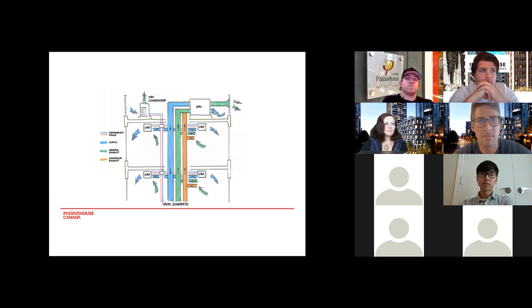The fourth point on this slide is that we didn't actually put in a heating or cooling coil on the discharge of the ERV, which is what I've typically done on a lot of my residential passive house projects. The reason is that we had a dedicated heating and cooling system in the building.